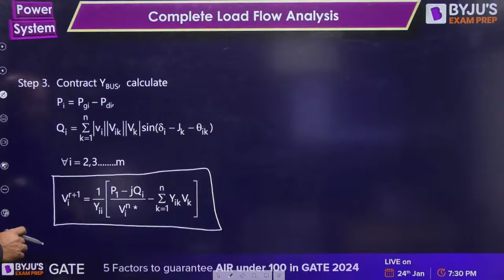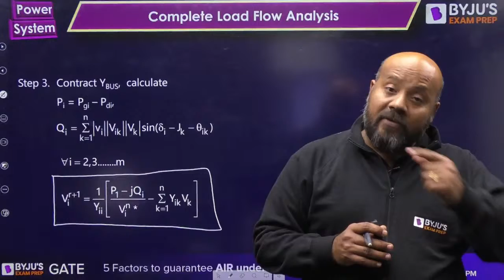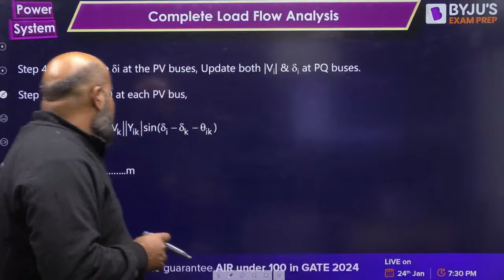A lot of confusion is going to be there, I understand. For the PQ bus, for every iteration you have to find the voltage magnitude and the phase angle. For the PV bus, at every iteration you have to find the Q value and the delta value, because P is known and V is known. So every iteration, every step, you have to find Q. By using the V equation, you can find the angle of V as delta. I hope you are getting that. This is how you have to proceed.